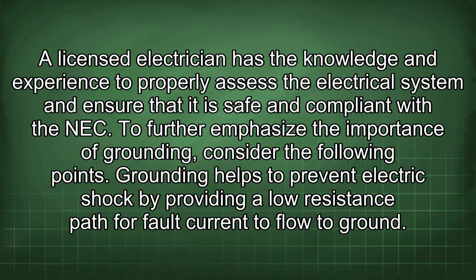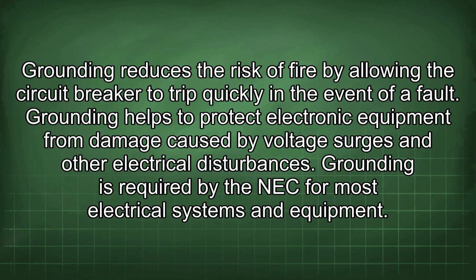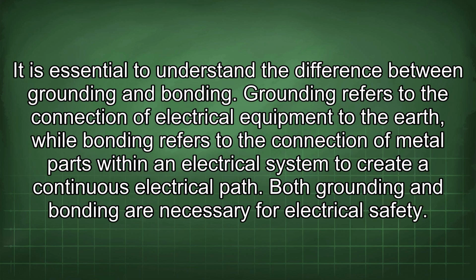To further emphasize the importance of grounding, consider the following points. Grounding helps to prevent electric shock by providing a low resistance path for fault current to flow to ground. Grounding reduces the risk of fire by allowing the circuit breaker to trip quickly in the event of a fault. Grounding helps to protect electronic equipment from damage caused by voltage surges and other electrical disturbances. Grounding is required by the NEC for most electrical systems and equipment. It is essential to understand the difference between grounding and bonding.